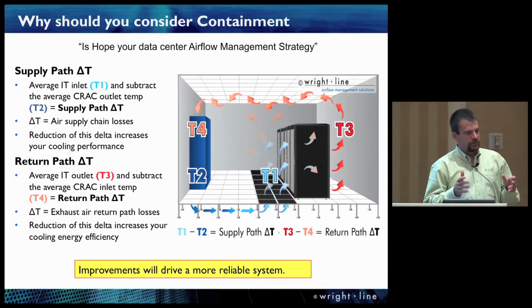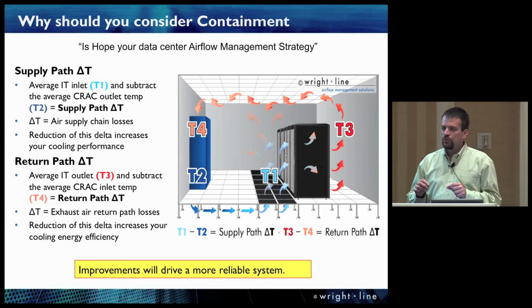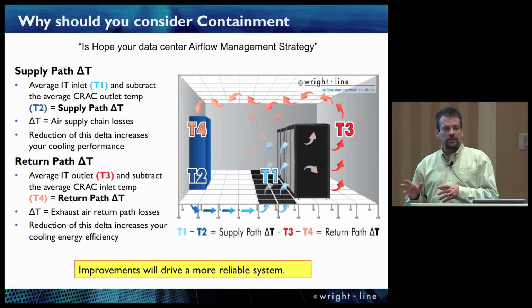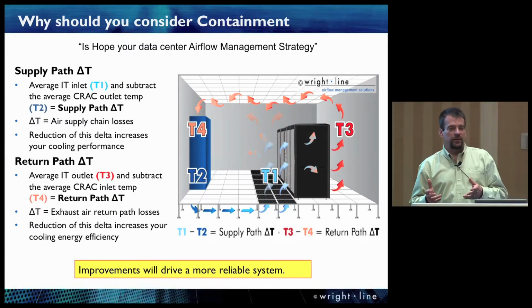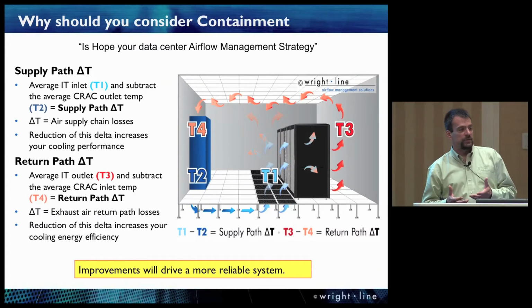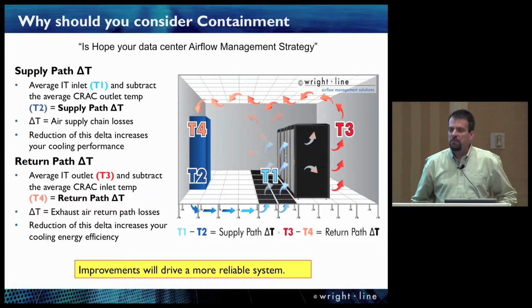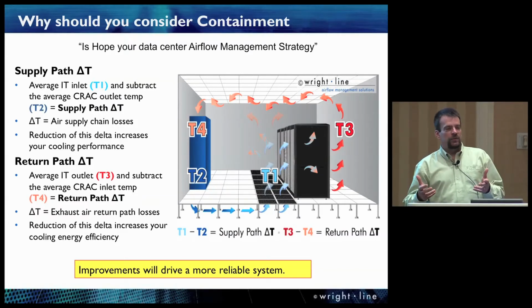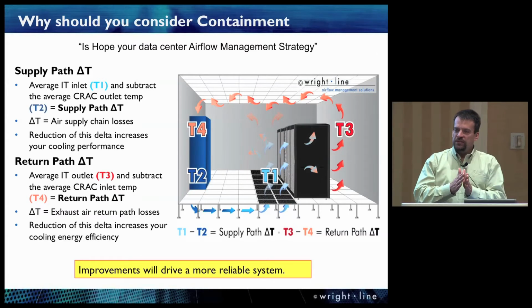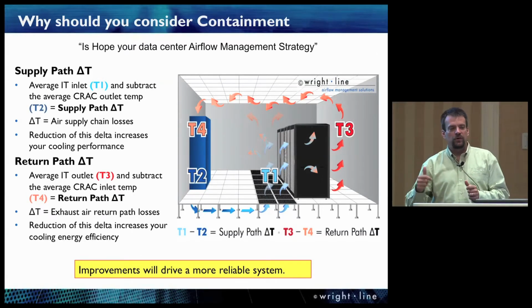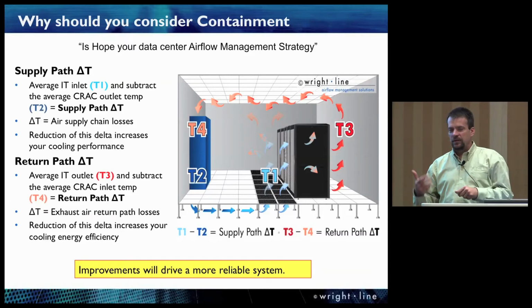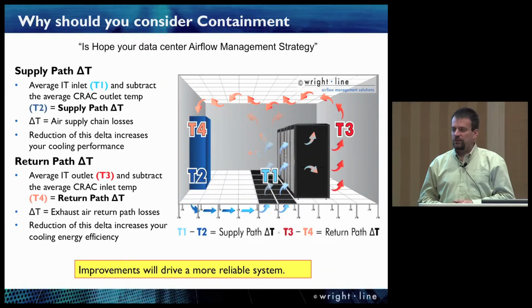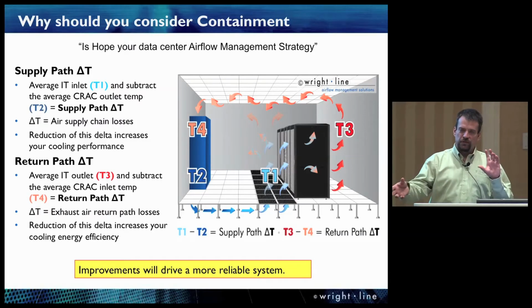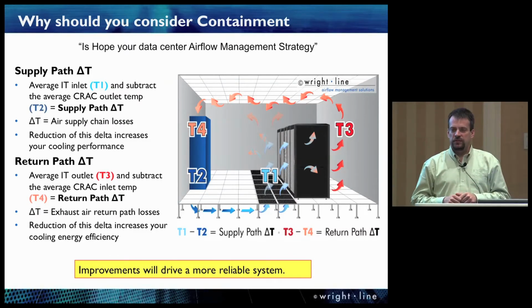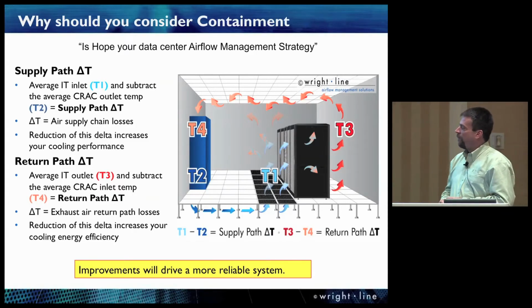As I drive solutions in the supply path delta T, that improves the cooling system's capability to cool the IT load. There are ways to overdo it, where you can create waste as well, and that actually happens in legacy data centers where all they do is supply a massive oversupply of air. Why are they doing that? Well, they're managing the supply path delta T to try to compress that and cool the IT equipment. However, the pain of that methodology on the return side is a really huge delta T, meaning the IT equipment's still putting out 90 and you're getting 72 back to your HVAC system. So a balance between managing supply path delta T and return path delta T is really what containment is about.